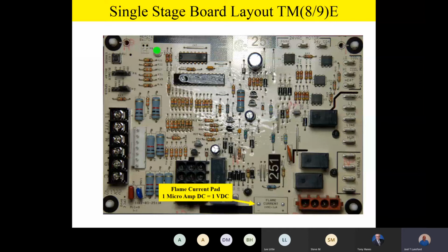So if you have an older home, make sure and double check that you've got a good solid ground all the way from the furnace to the power panel, and then bonded down to earth ground, because if you don't have a good ground, you won't have good flame sensing, and then of course you're going to have erratic operation with the furnace. Any questions or comments so far on what we've covered?